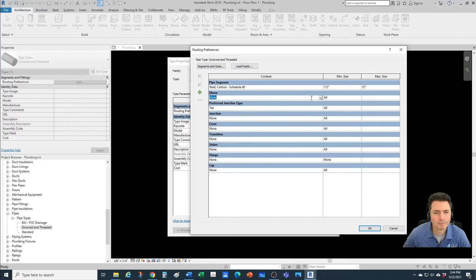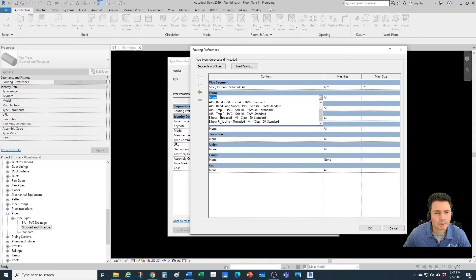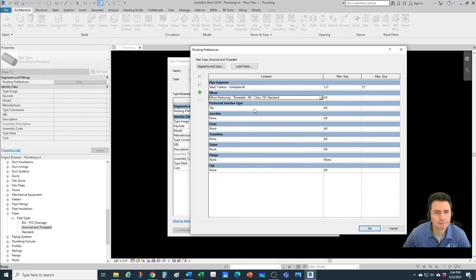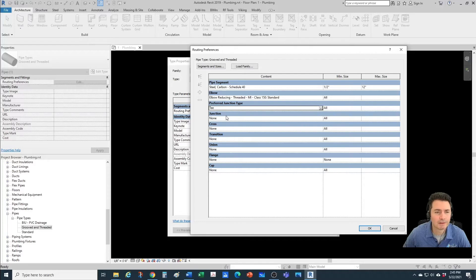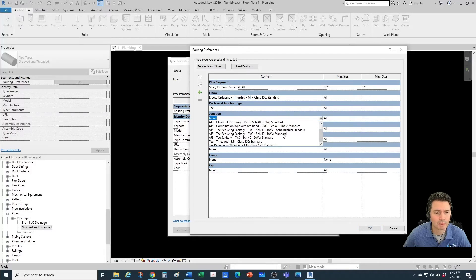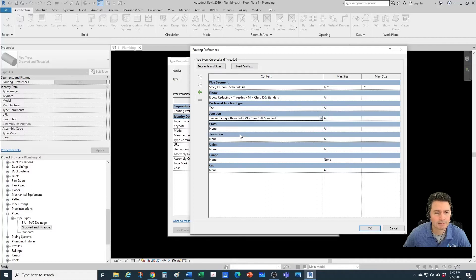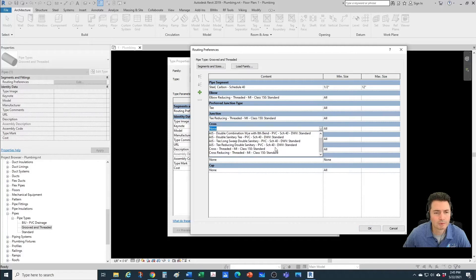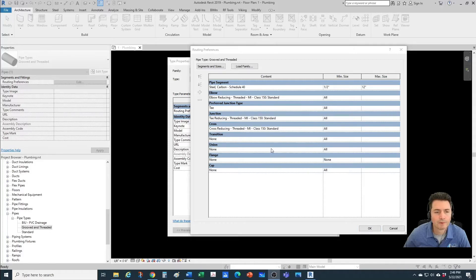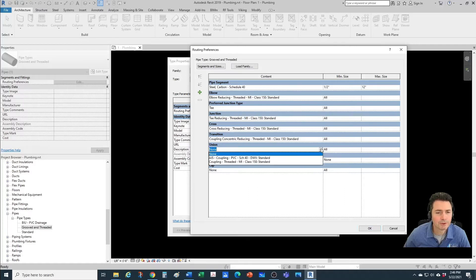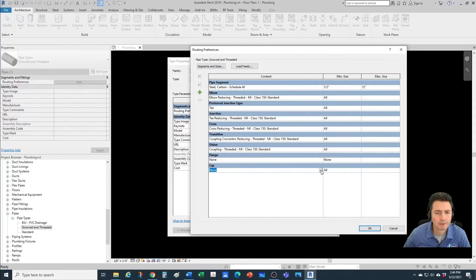Also a T and a reducing T. Now let's start selecting those in the routing preferences. For our elbow we're going to go with the reducing threaded so we have the option to reduce from, say, one inch to half inch. The preferred junction type we'll keep as T. For the junction type we're going with the reducing T threaded. For cross we'll select the reducing cross. For transition we'll select the coupling concentric reducing. For union we'll keep the coupling threaded and no flange. For cap we'll select our threaded cap.